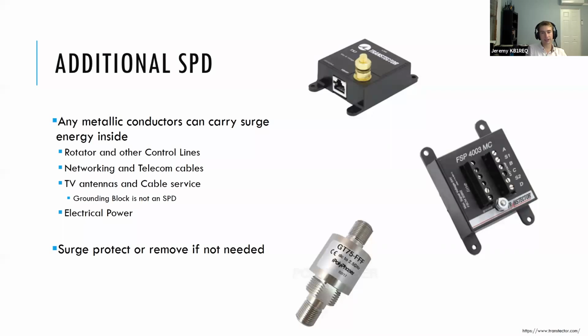Some examples are listed here. Some SPDs for various types are shown. I've got an Ethernet surge protector. This one on the bottom is a surge protector for a 75 ohm cable, for a TV antenna, or for your cable service coming in. The grounding blocks that we see typically in a cable installation, that's not a surge protector. It's not a substitute for a surge protector. You could think of that more as a ground kit. That's essentially what it's doing. It's grabbing the outside conductor there and grounding it, which is a good thing. Those help, but it's not a substitute for something that's going to protect the center conductor.